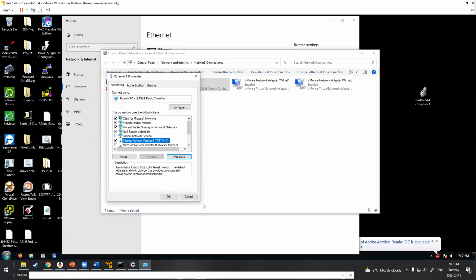We're not quite sure what it was, but that server they dropped on site had a DHCP server enabled, and it was issuing DHCP addresses, and it assigned DHCP addresses in a range of addresses that were already being used in the automation system.